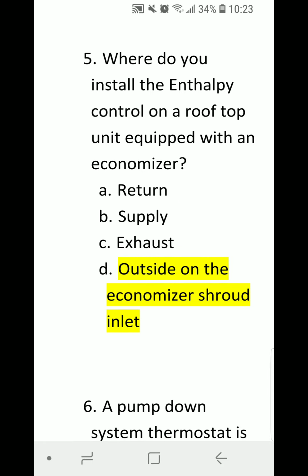5. Where do you install the enthalpy control on a rooftop unit equipped with an economizer? A. Return, B. Supply, C. Exhaust, or D. Outside on the economizer shroud inlet. The correct answer is D. Outside on the economizer shroud inlet.